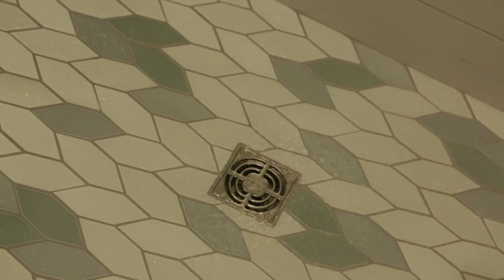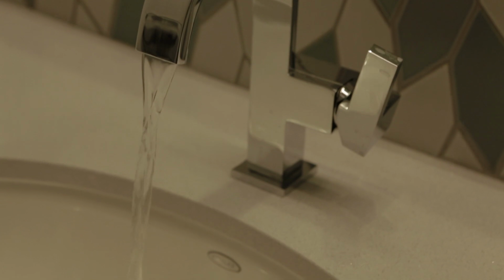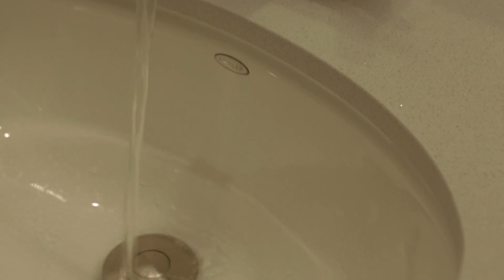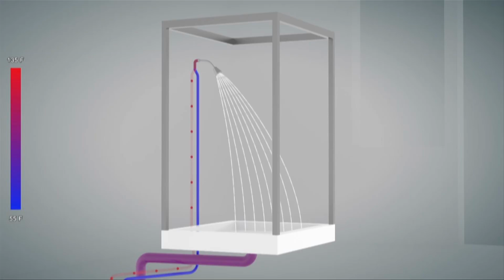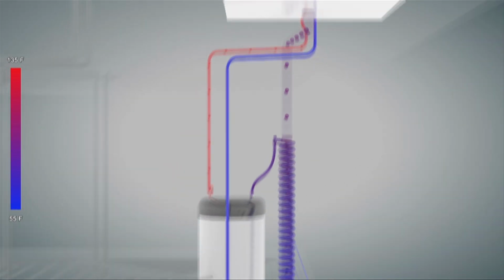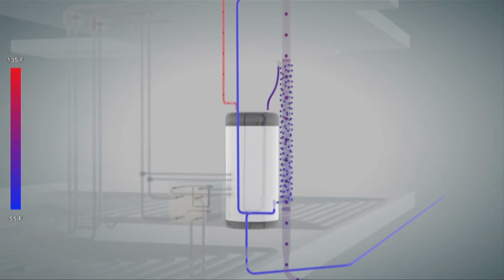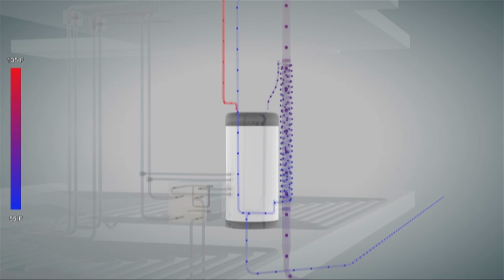As hot drain water from our showers, tub, and sinks upstairs drains down towards the gray water system, we take the cold water coming in to refill our domestic hot water tank and run it through a counterflow heat exchanger. It picks up a significant amount of the heat that would otherwise just go straight out to the sewer.